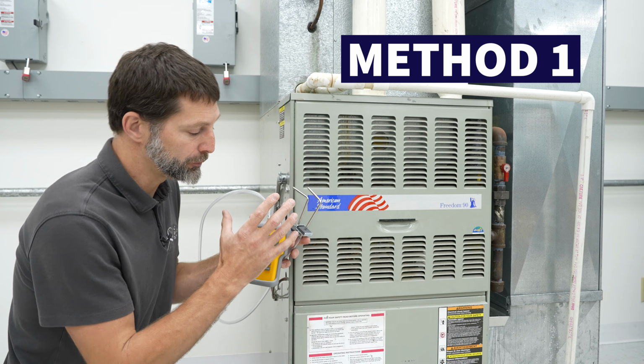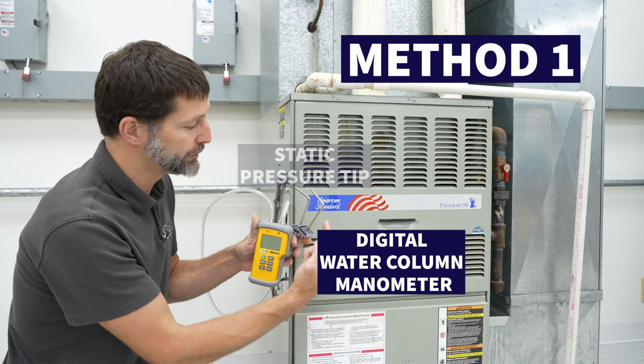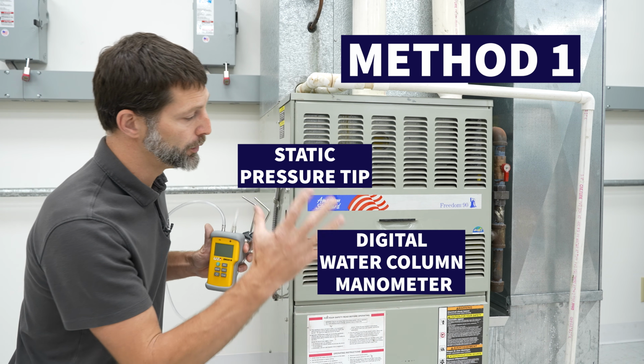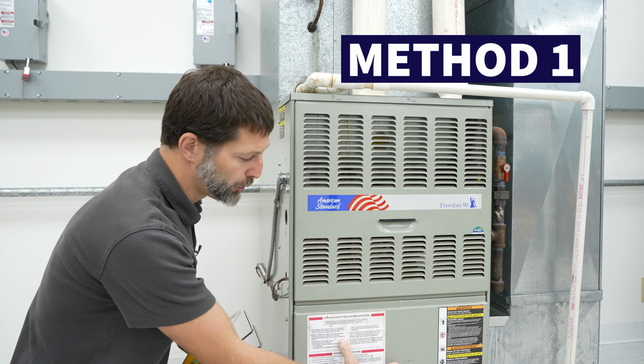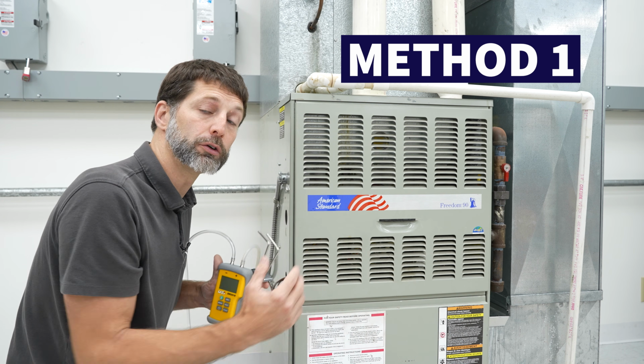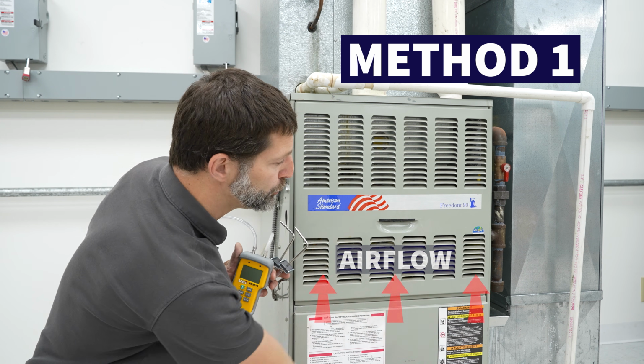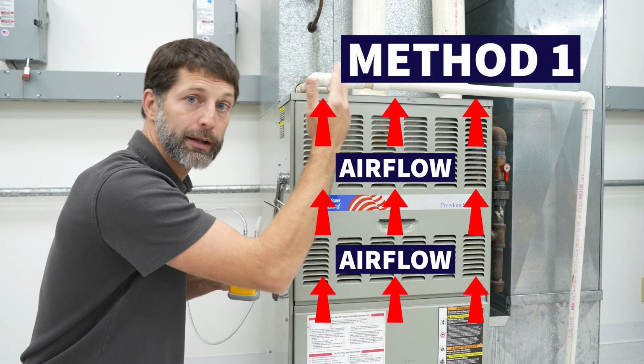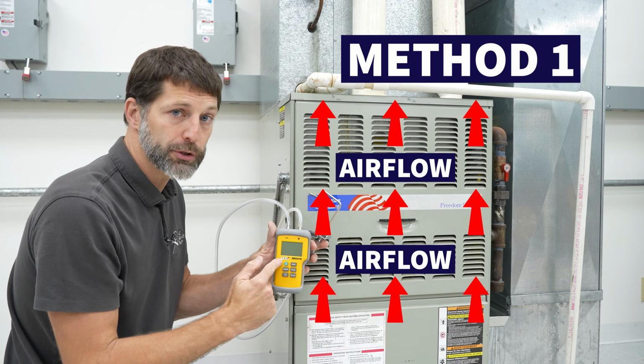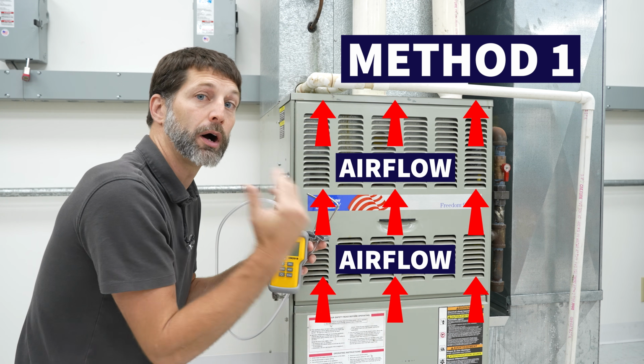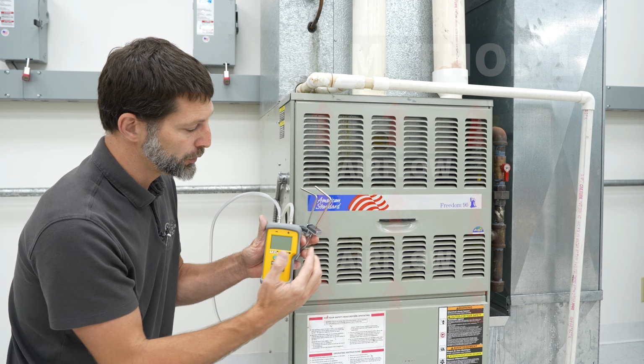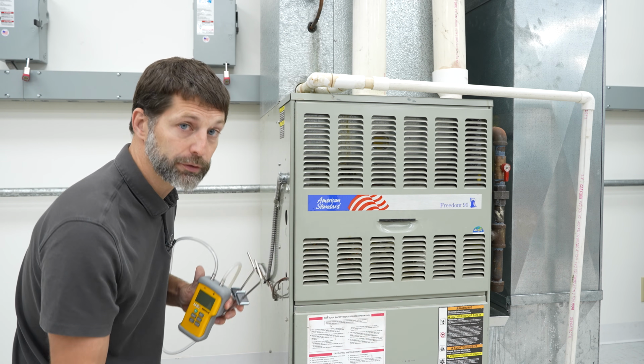Our first method involves using a digital water column manometer and static pressure tips. This unit has a blower motor down here, and that blower motor has to exert a certain amount of pressure in order to move the airflow across the furnace and AC coil, so we can measure the static pressure to see if it's too high. We can do that with a 2-port digital manometer or a single port like this.